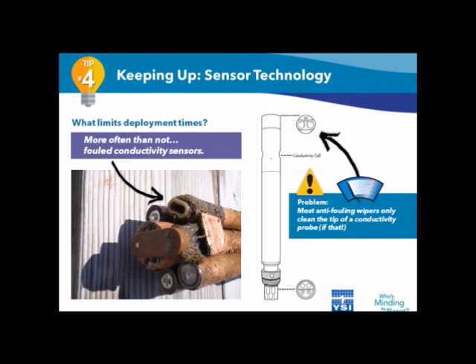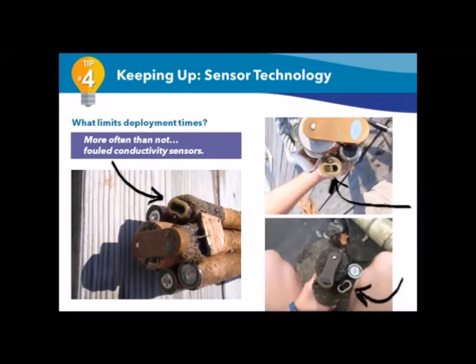And many of these sensors have their electrodes buried deep within the probe, far out of reach of any kind of anti-fouling wiper like Tiffany talked about or copper accessory that Tom mentioned. When obstacles like small aquatic life or clumps of sediment or even algae build up within these closed-off conductivity cells, that really interferes with the measurement.